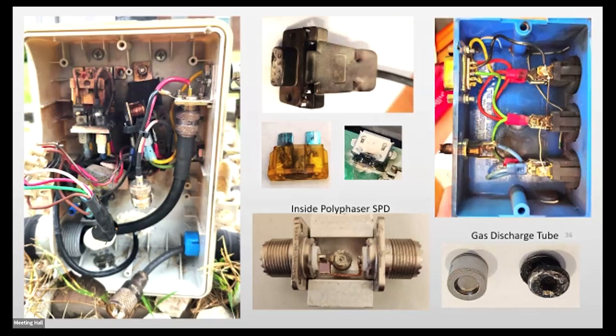I just wanted to show you what's inside a polyphaser device itself if you've never taken one apart. They aren't the easiest to take apart, but you can pull them apart and replace that element if you ever have to. You can see the gas discharge tube on the left is the new one, and the one on the right is the one that got hit. That's what's laying up here on the table.